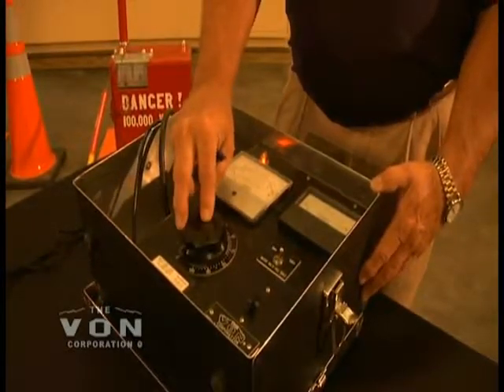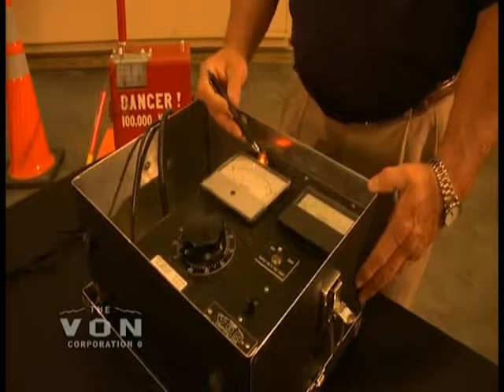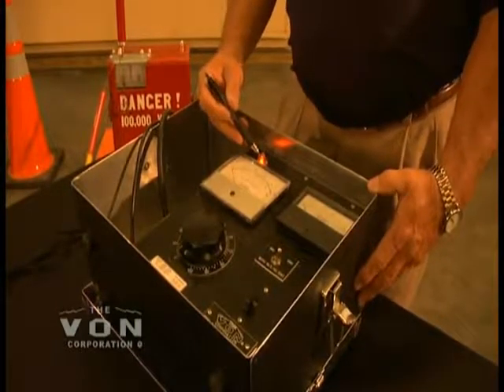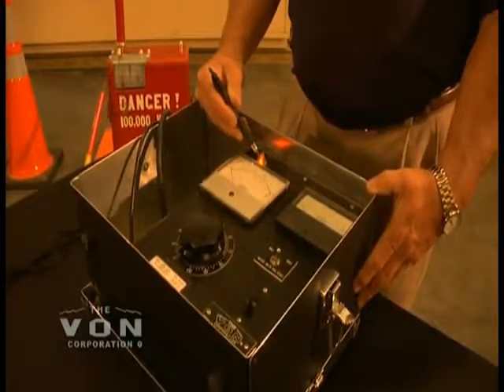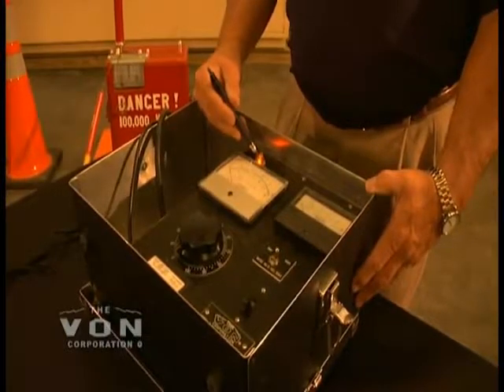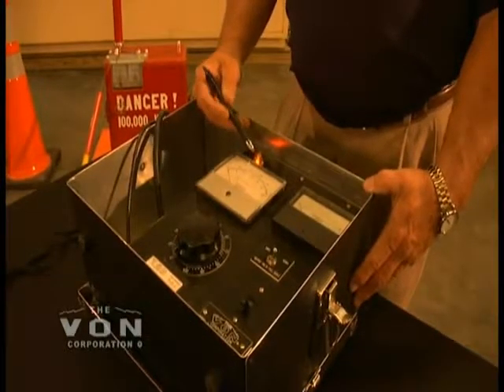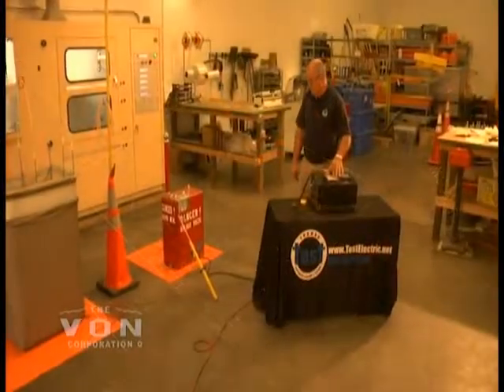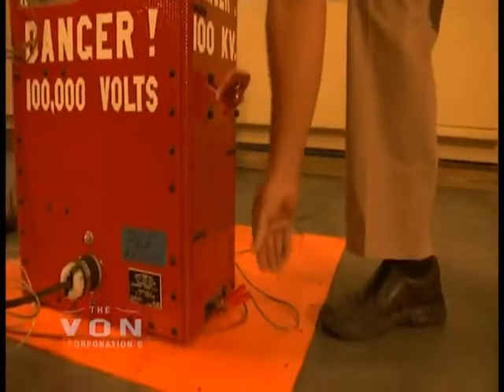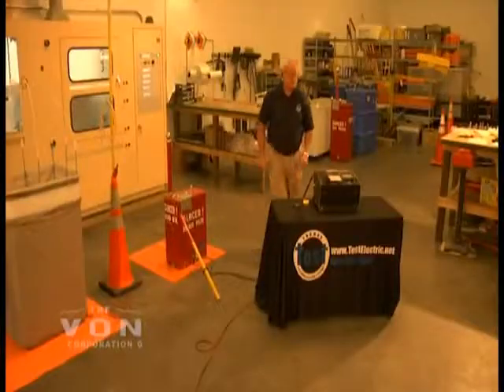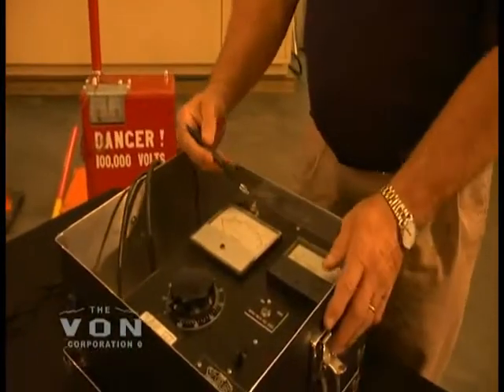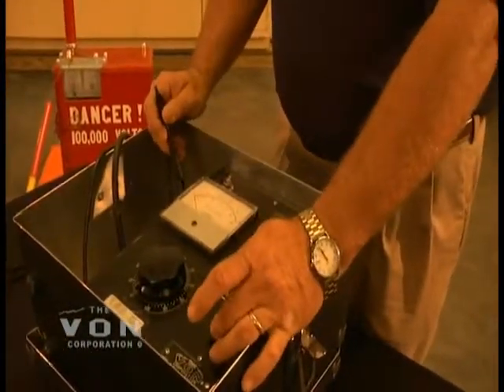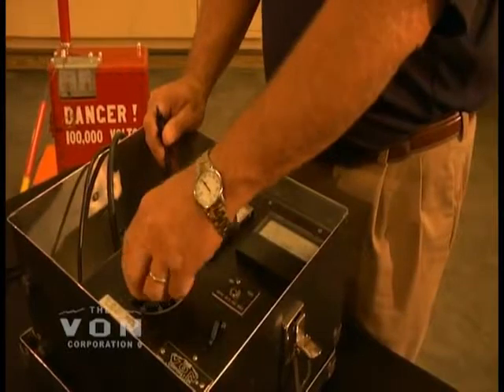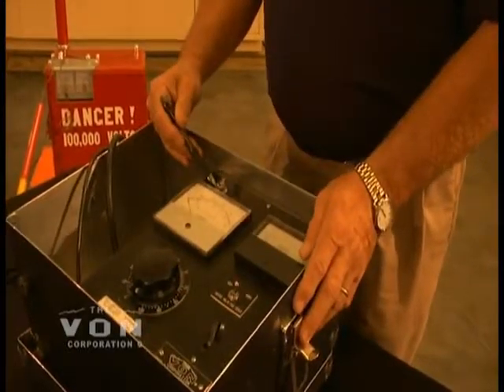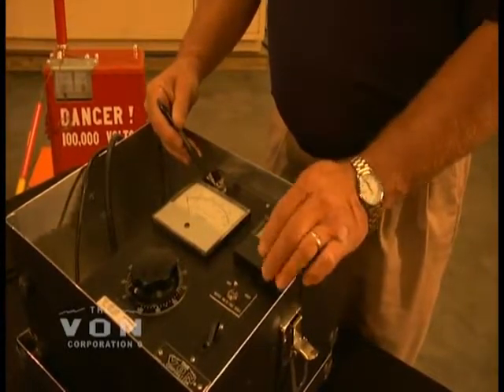And this is a ground relay light. This light is connected to a ground relay, which shows you that the unit is grounded properly when the light is on. If the light is off, it is not grounded properly. If the unit is not grounded properly, when you turn it on, it will not operate at all unless the ground relay is closed in. And when the ground relay is closed in, then this light will also come on.